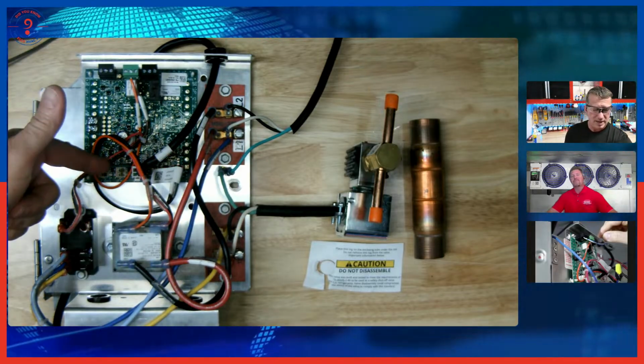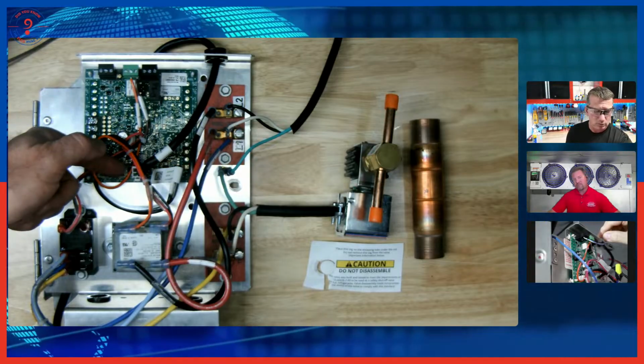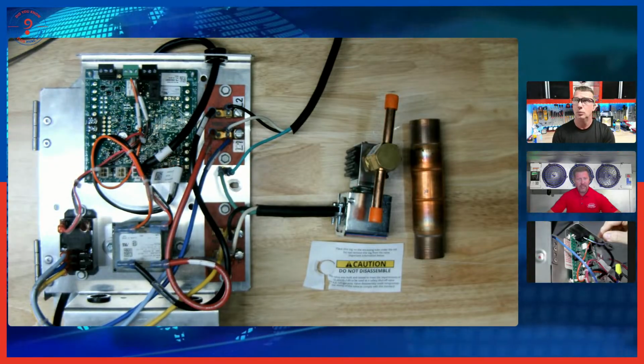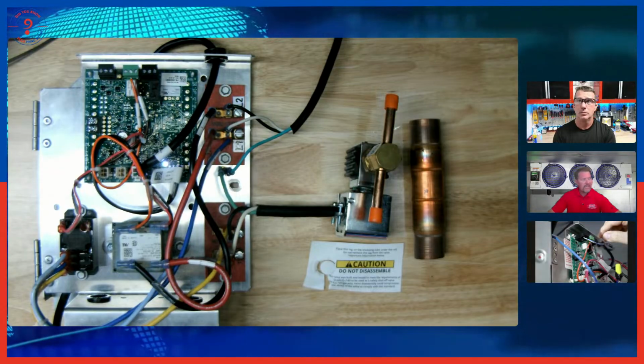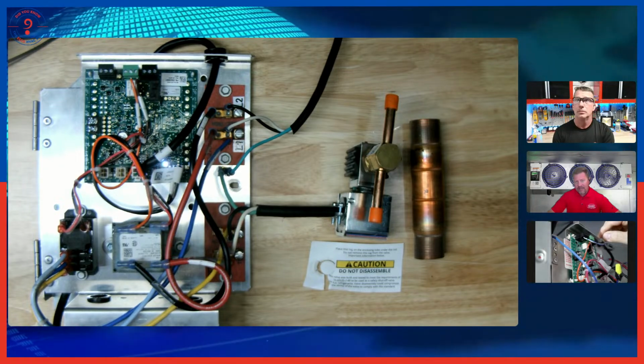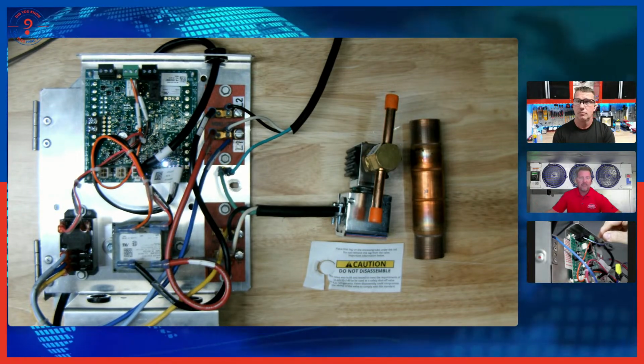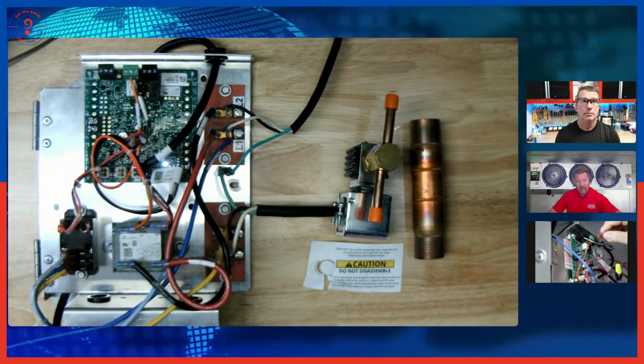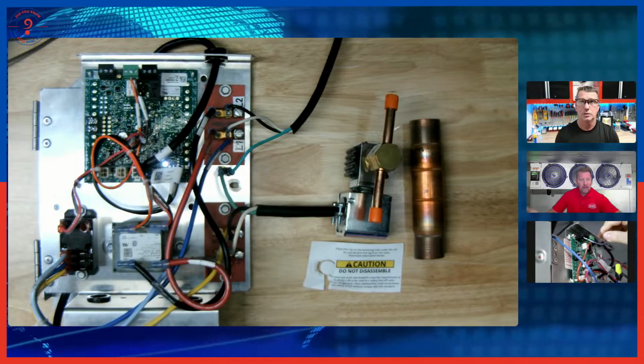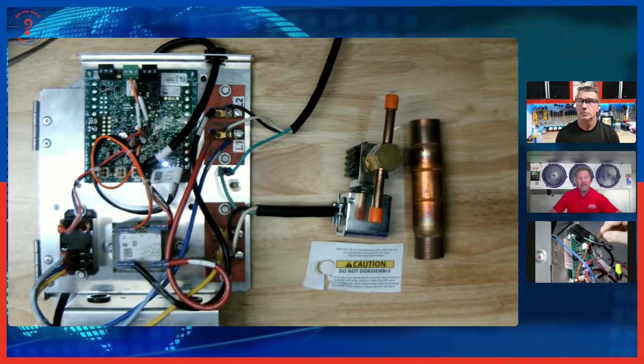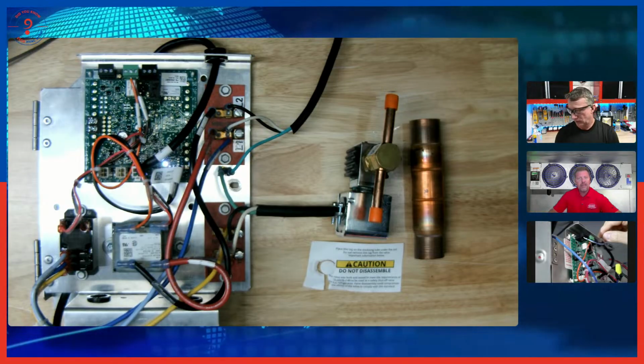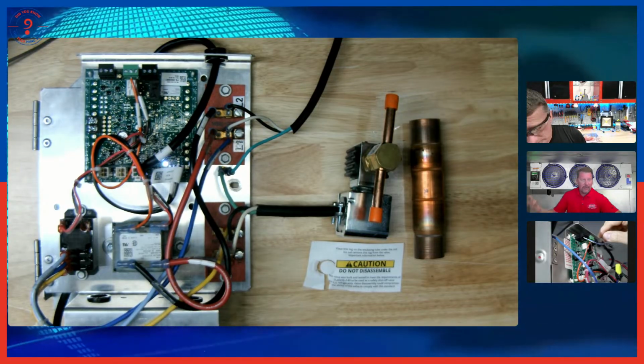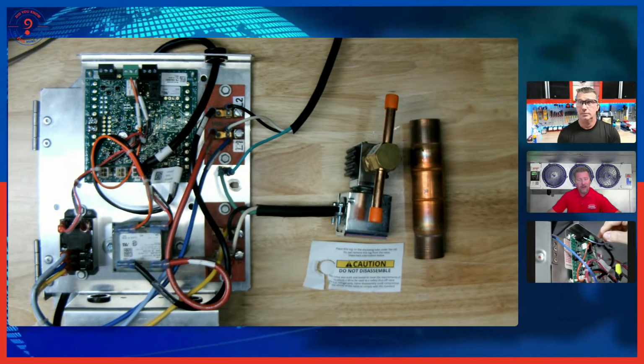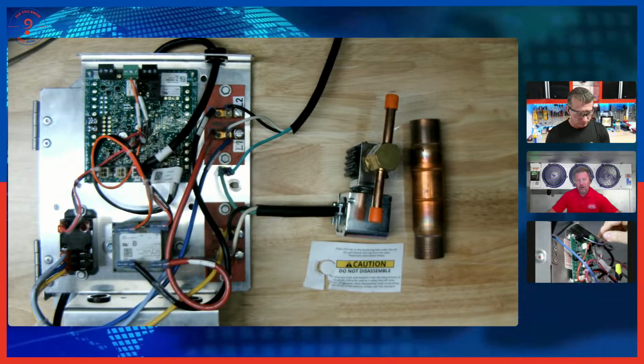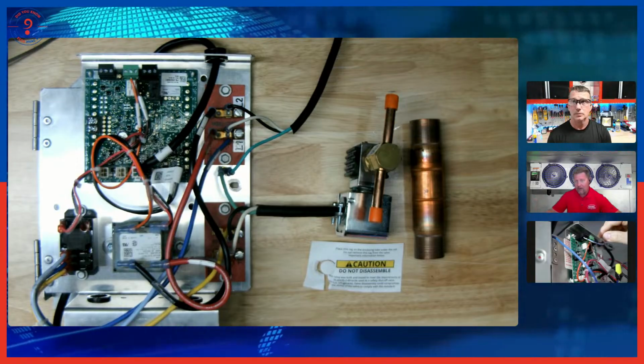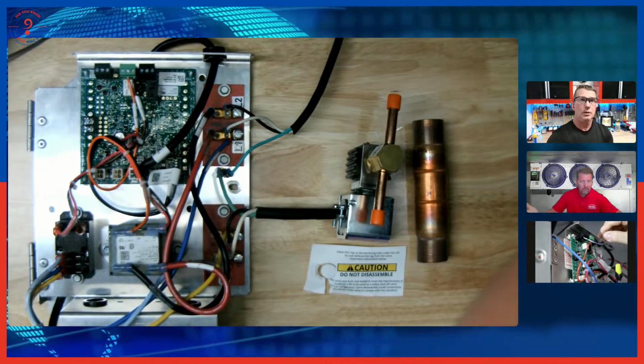And I did notice we actually have additional plugs for refrigerant detection sensors on this board. Yes, so we can use up to 3 detectors on here. And again, our detector on these is going to be located near the bottom, near the drain pan, because A2Ls are heavier than air. If you have a leak in your coil, your A2L is going to generally migrate downward, and that sensor is going to pick it up there. We didn't put it at the top of the coil because your A2Ls aren't going to be there. Just like with propane or any other flammable gas, they're heavier than air, so you generally are going to find them near the floor or near the bottom of the pan.